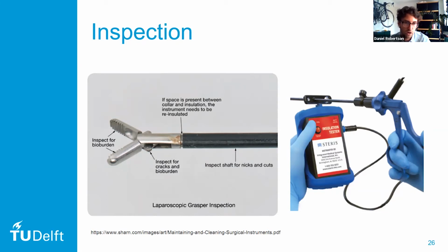We saw a few times in some of the hospitals that instruments that had damaged insulation were used for parts of the procedure that you were not going to use electrocautery on. But the problem with this is that if you have a cracked piece of insulation, you can get microbes that will grow within the cracks and under the insulation. So it makes them very, very difficult to clean.